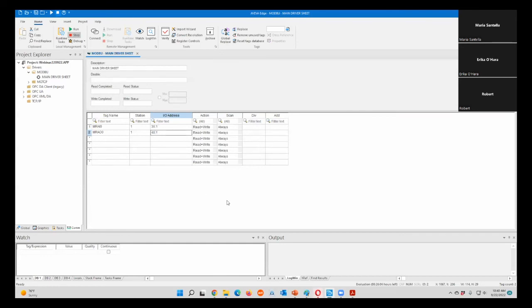We click OK. The next thing we'll do is add one more analog input tag. Oops, I keep double clicking by mistake. MRAI1. And following the Modbus address table, the AI would be 3x colon 2. Notice the tag names are 0 and 1, but the addresses are 1, then 2. If we had an AI2, it'd be 3x colon 3. These are actually read only, so we'll just make them read. You don't necessarily need to do this, since the hardware itself limits it anyway, but just for being correct, I will do it here.